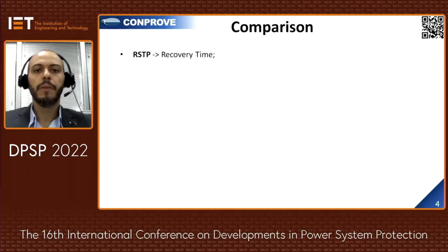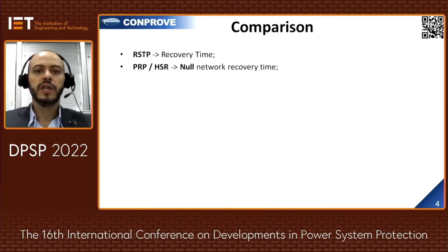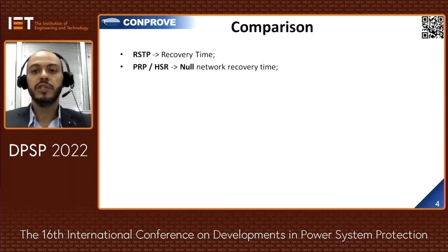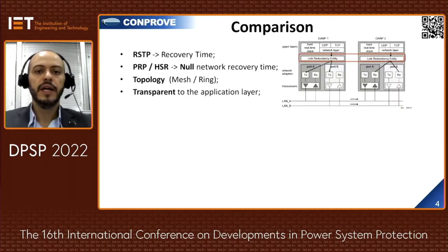Comparing the three protocols, RSTP has some recovery time because if the communication path is lost, the algorithm must calculate another one and that takes time. PRP and HSR have no recovery time because the information is already duplicated. The main difference between PRP and HSR is the topology: PRP uses a mesh and HSR a ring. PRP needs to use switches, whereas in HSR there is no such requirement.